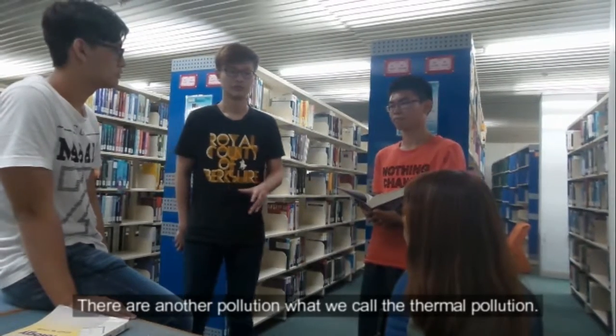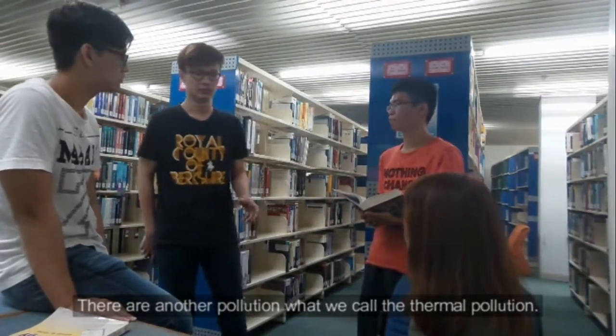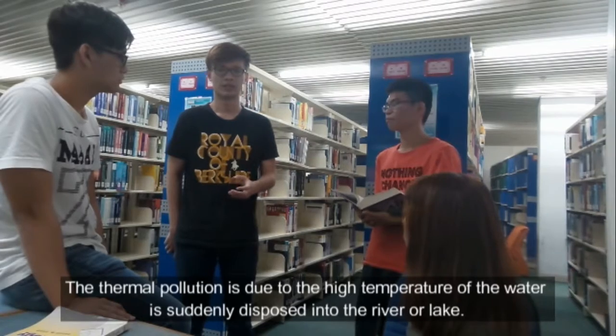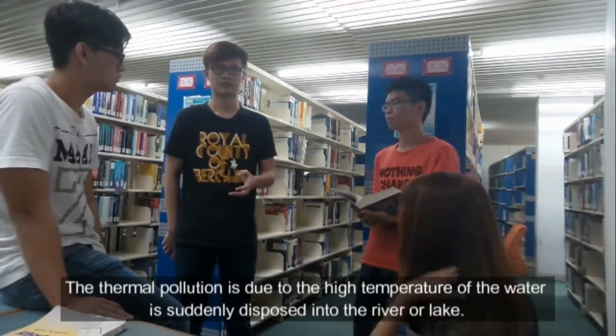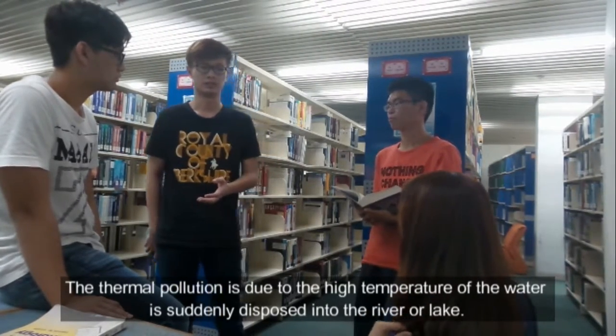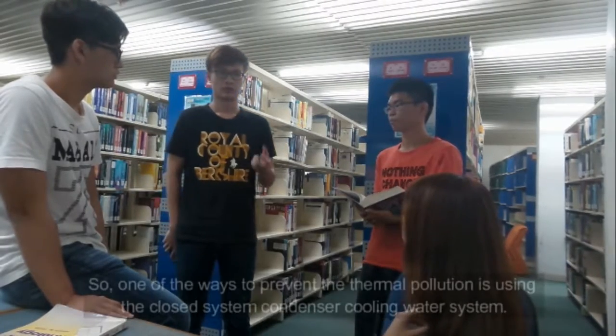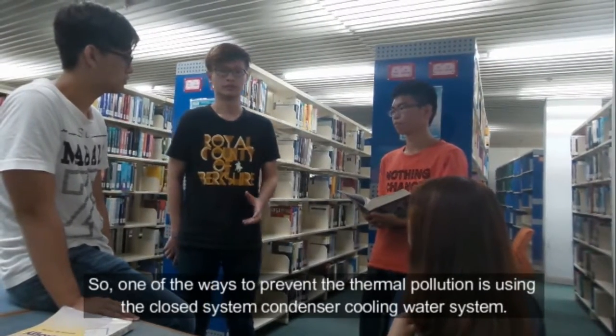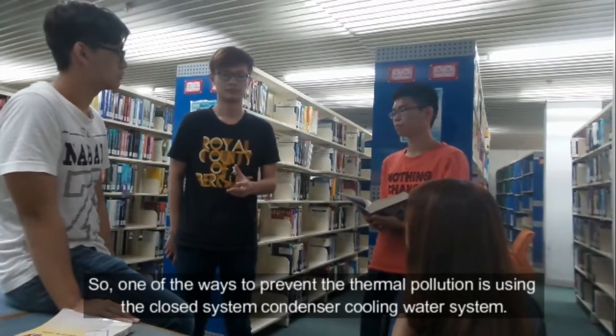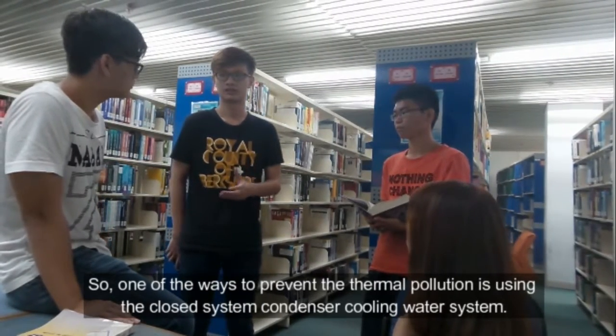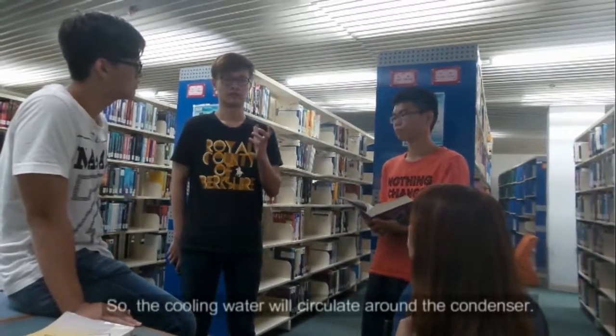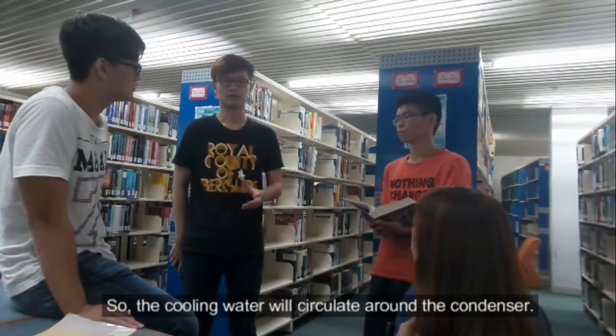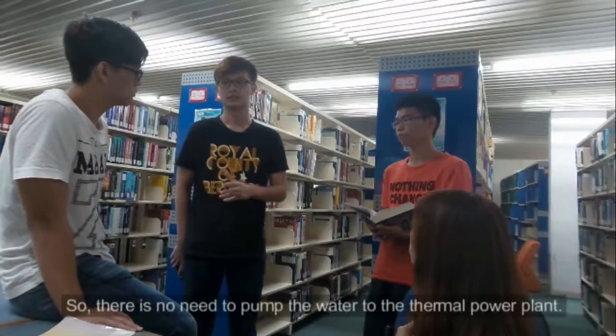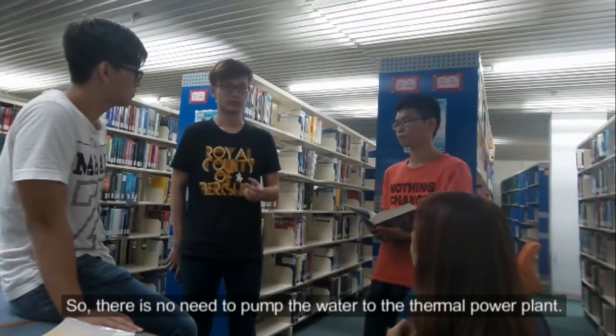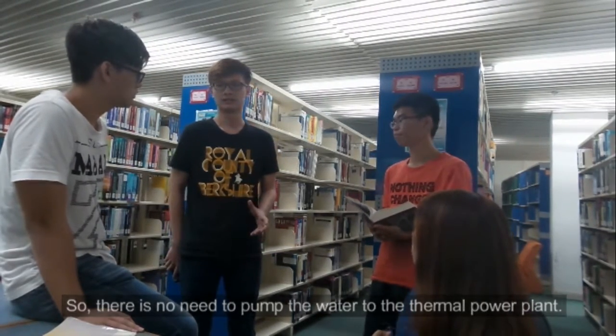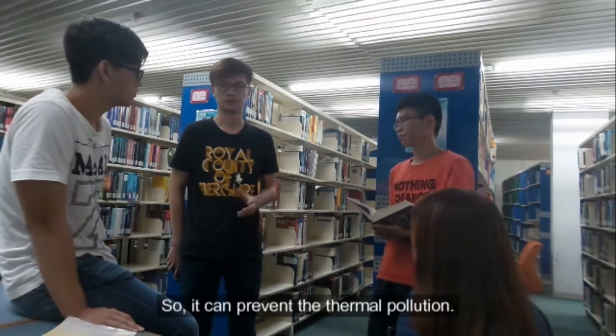There is another pollution, which we call thermal pollution. Thermal pollution is due to high temperature water being suddenly disposed into a river or lake. One way to prevent thermal pollution is using a closed system condenser cooling water system. The cooling water will circulate around the condenser, so there is no need to pump the water out of the thermal power plant. So it can prevent thermal pollution.